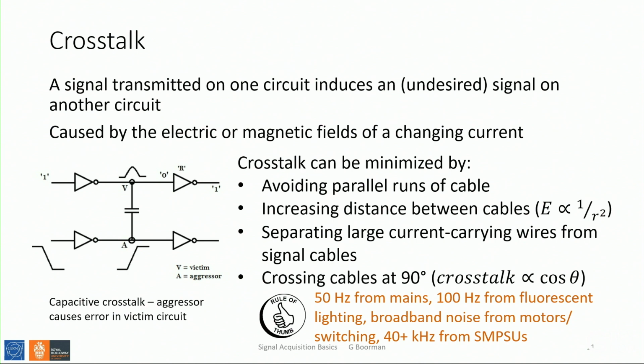The kind of effects you will actually see: if you see a 50 hertz signal, that's from mains. 100 hertz is usually from fluorescent lighting. Motors and switching - that's broadband, particularly once brushes on motors wear out, you get a very broad band of noise, 40 kilohertz to 80 kilohertz, sometimes a bit more. Switch mode power supplies - you can see all of these effects. So when you look at your signals and see something like this, these are the likely sources, so you know to route your signals - acquisition signal, clock signal, trigger, whatever it is - away from these noise sources.